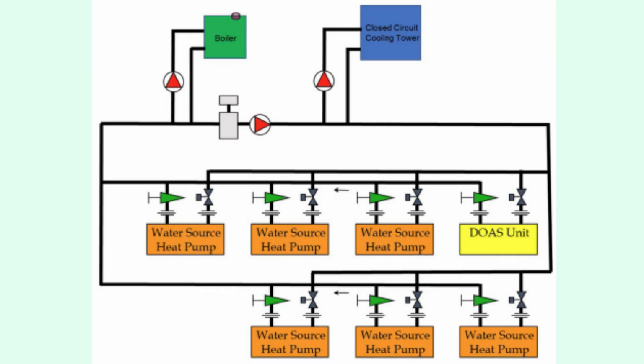It uses condenser water circulating through a hydronic coil to reheat the dehumidified air. With hot water reheat, a modulating valve and proportional controller fine-tune water flow through the coil, keeping the supply air temperature and room conditions steady and comfortable at all times. In summary, whether you use a DOAS, an ERU, or integrated WSHP reheat, the goal is the same. Deliver dry, conditioned outdoor air to maintain indoor comfort and system efficiency.